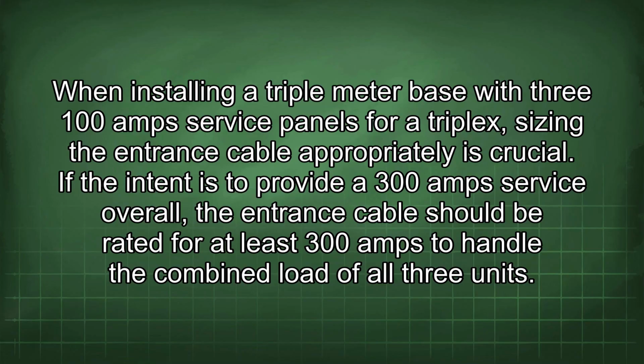When installing a triple meter base with three 100 amp service panels for a triplex, sizing the entrance cable appropriately is crucial. If the intent is to provide a 300 amp service overall, the entrance cable should be rated for at least 300 amps to handle the combined load of all three units.